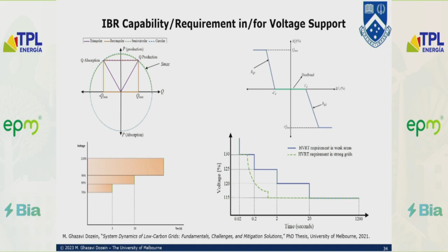This is the requirement, but can inverters actually do that? Maybe not - you ask them to provide this voltage support, but it may not be possible. This is the event that happened in November 2019, please have a look at this report. Following a voltage disturbance, we got around 300 megawatts of PV tripping, so they couldn't really comply with the grid code requirements. That's also a big challenge.